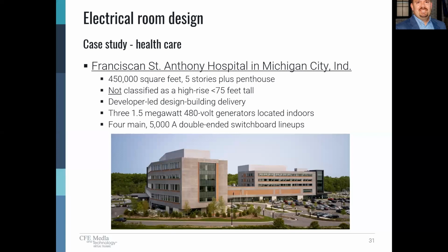In terms of electrical distribution in the building, we had 3 1.5 megawatt generators located indoors to the building and 4 main 5,000 amp double-ended switchgear lineups. The campus also has a medium voltage distribution outside the building that fed the interior distribution as well.